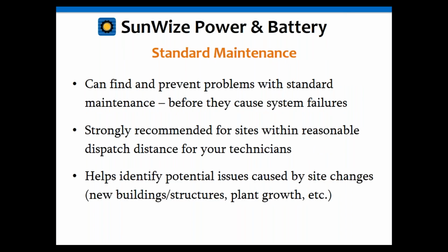Okay, as I mentioned, you should do maintenance, and it's very important to go through that first. You'd be surprised at just how many problems you can prevent and find just by doing some basic standard maintenance. So we're going to start with that first. The other thing I want to start with is that maintenance should be done approximately every 6 months to a year, definitely annually, generally twice a year. We usually recommend in the spring and the fall. The reason for that is usually coming out of the winter, you might have some problems. And then going into winter, you want to make certain your system is good. So those are two good times to do maintenance.